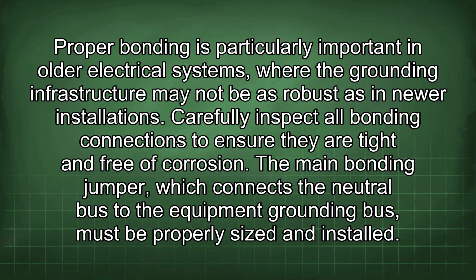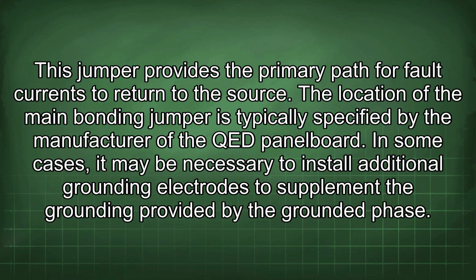The main bonding jumper, which connects the neutral bus to the equipment grounding bus, must be properly sized and installed. This jumper provides the primary path for fault currents to return to the source. The location of the main bonding jumper is typically specified by the manufacturer of the QED panel board.